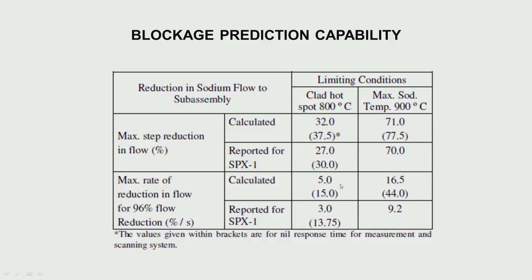For the slow flow reduction case of 96% flow, the rate our model could accept to reach 800°C was 5% per second, whereas they reported about 3% per second. For the other case, we got 16.5 as the end point. There are some differences because we don't know the exact data — literature doesn't give complete data. Nevertheless, the trends are good and we are not very far from what is happening. This gave us confidence that we are able to predict the core conditions well.